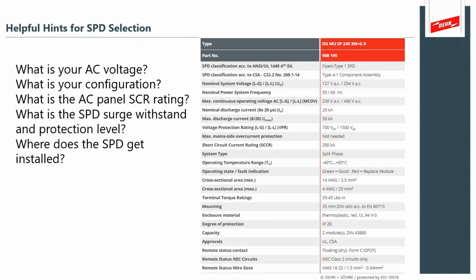So some hints about selecting SPDs. Of course, the manufacturer's websites are all a little bit different. There's several things to look for to make sure that you're picking your device the proper way. You're looking for your AC voltage. You're looking for the configuration. Is it something like 120/208, 120/240 split phase? What's the system that you're looking at? What is the SCCR, the short circuit current rating of the AC power system? Remember, the SPD has to match what your system short circuit rating is.